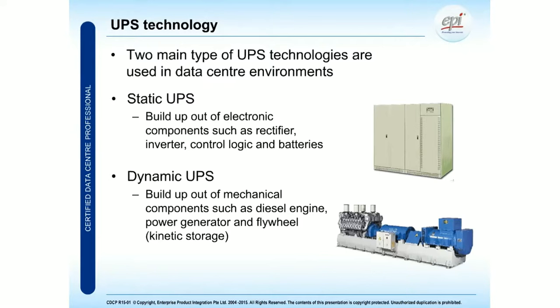Now we talk about two different types of UPS systems. In this picture, we can see two different systems. One of them is the static UPS system, which is being used in many data centers all across the world. This basically consists of two or even more cabinets. Inside one cabinet, there is a switchboard, and there are some control logics installed, and some levers and some breakers. Inside the second cabinet, or many of the other cabinets as well, the batteries will be installed. We have many different types of batteries that we talk about in the CDCP as well. They all have their own pros and cons. It depends on your initial investment, on your ambient temperature, on the lifetime, the life cycle of your batteries as well, which system you should be applying for your business.